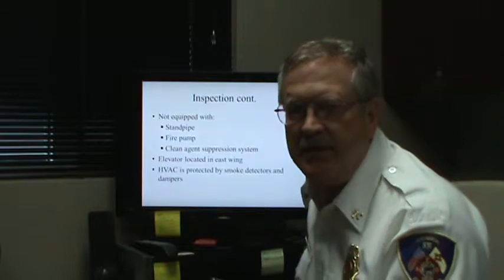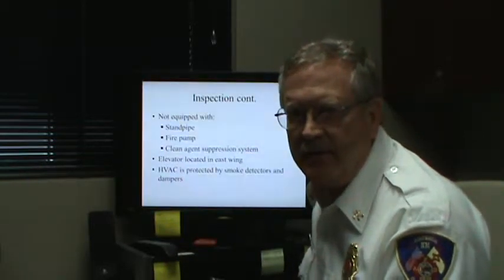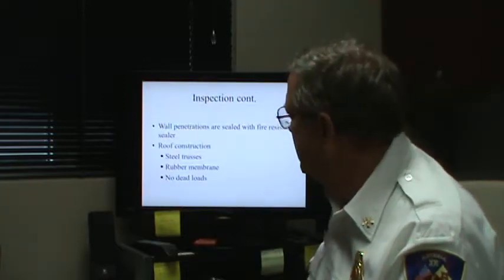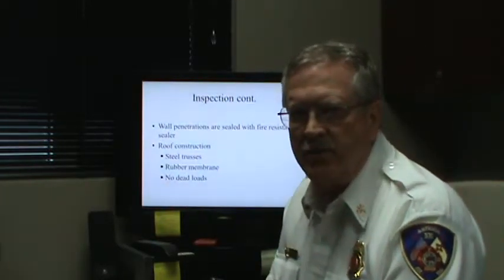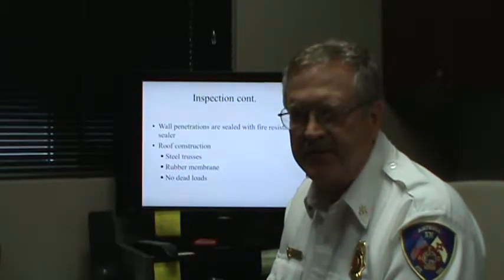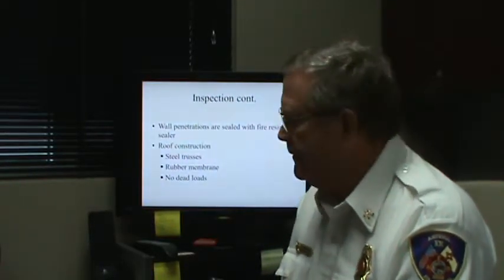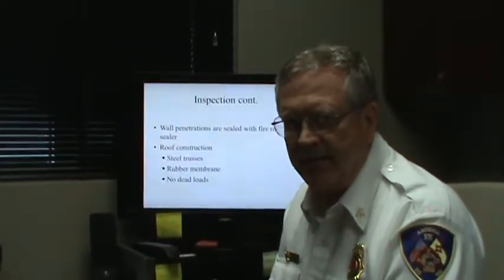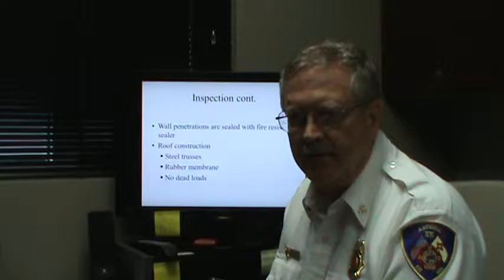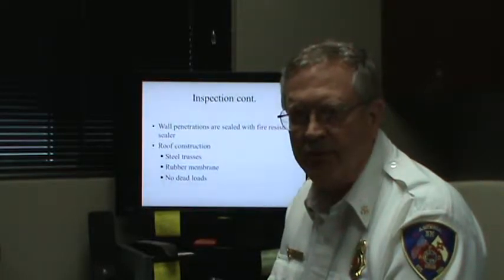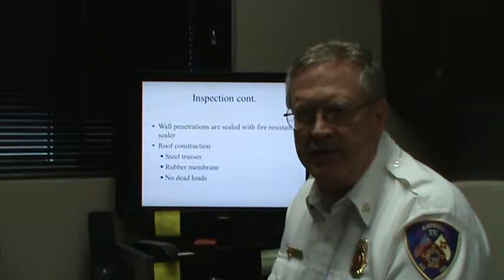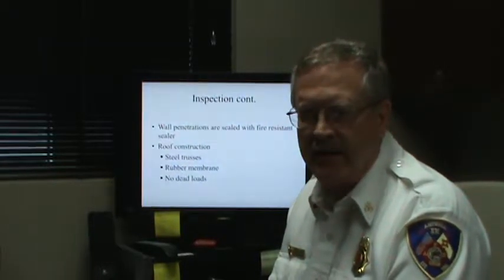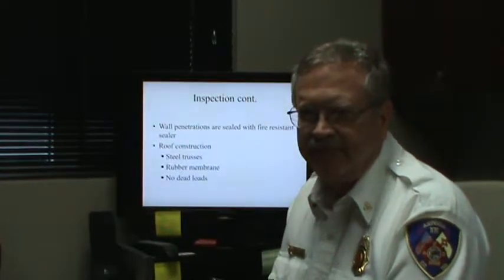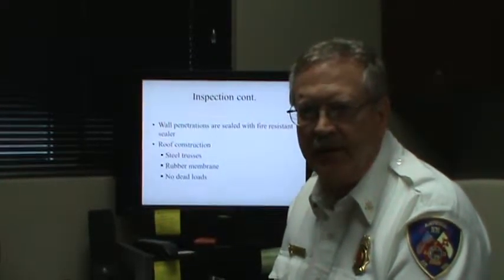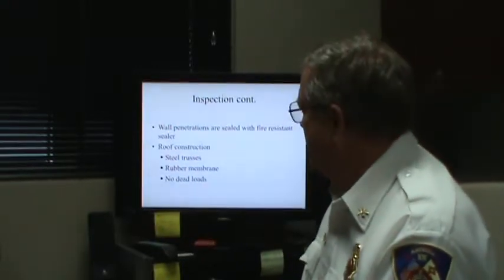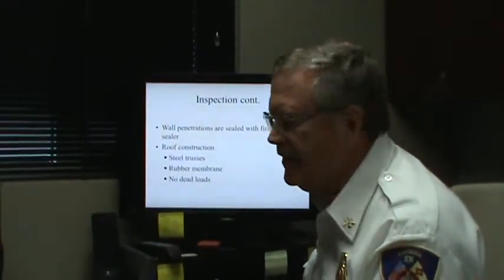The HVAC system is protected by smoke detectors along with the dampers in the vents. The wall penetrations were sealed with fire resistant sealants. The roof construction was steel trusses. They're covered by a rubber membrane. The dead loads that we normally see up there were moved down to the ground level for easy maintenance, and also just to get them where they could be worked on and change the filters and whatnot there. So there's really actually no dead loads up there.